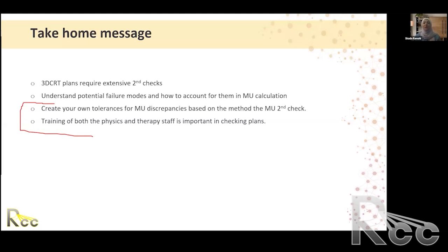And you have to be very careful now how you commission your planning system. Be safe. You measure in water. So report dose to water. That would be 1 centigray per monitor unit. How the equation changes, that requires a kind of separate series of lectures on how to build the monitor unit equation depending on different scenarios. Just keep in mind, we need to know where the LINAC was calibrated, and everything is correcting to take you back to the calibration geometry.